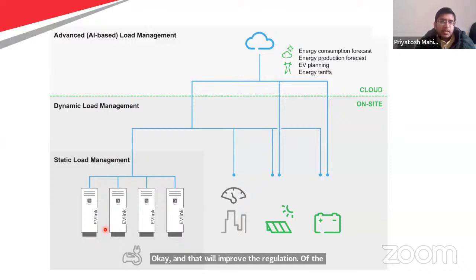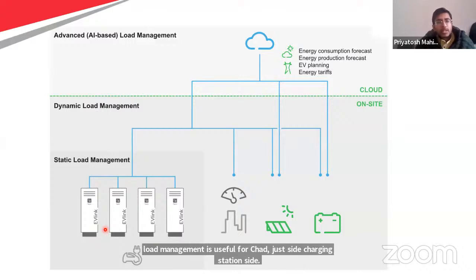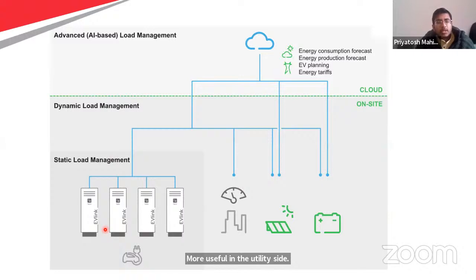So very precisely, I can say that dynamic load management is useful for the charging station side, but more useful on the utility side. You may think as an owner that you don't have a problem if your demand fluctuates, but the utility will not allow you, or they will penalize you if you are the reason behind the impact on their regulations.